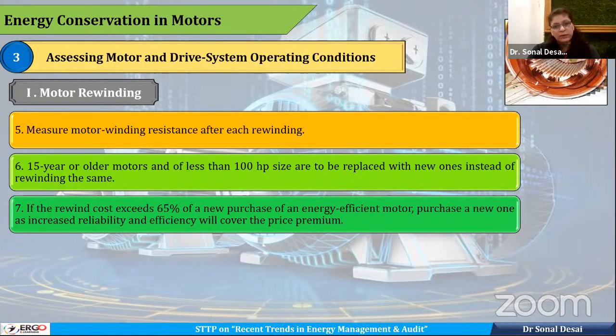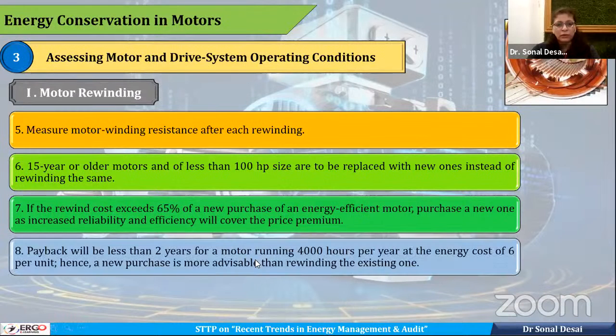If the rewinding cost is more than 65% of the purchase cost, right? If your motor cost is 1 lakh rupees and rewinding cost is 65,000 rupees, then rather than going for rewinding and saving those 35,000, go with the new one. It will have a payback of less than 1.5 years. So it is just said that payback will be less than 2 years for a motor which is running for 4,000 hours per year, and energy cost is 6 rupees per unit. So it will be even lesser for 7 or 7.5 rupees electricity cost.